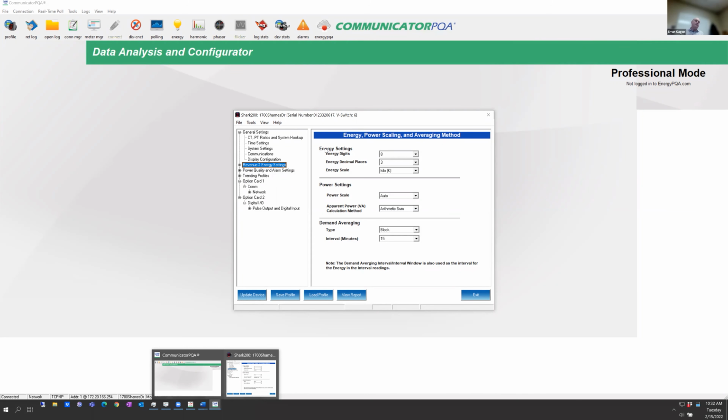So what does that mean? Line frequency is the actual cycles of frequency coming in on the power line. Now, the law is this: utilities in general have to provide you 60.0000 hertz at the end of a month, right? So they can go a little faster, they can go a little slower, but they have to count up all their frequency cycles and provide you a normalized frequency at the end of the month.